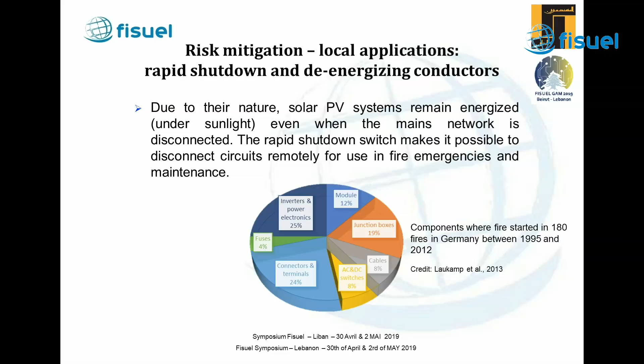General best practice measures were applied at all sites as much as possible, including electromagnetic loop reduction, equipotential bonding of all exposed metal parts, proper material use for cable heads, and proper crimping and power cable connection, which is one of the highest causes of fires in PV systems. Last but not least, operational maintenance and regular checks for the system.